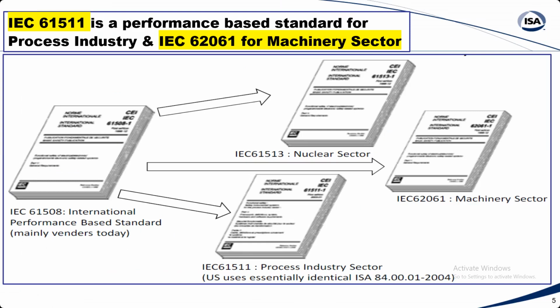Now, ISA 84 and 61511 have identical clauses, absolutely identical clauses, except some additions because of the prevailing regulations of OSHA and EPA in America, which were then in ISA 84 but not in 61511. But now, as on date, ISA is in totality following IEC 61511. They call it ISA IEC 61511. So we'll discuss more about that.